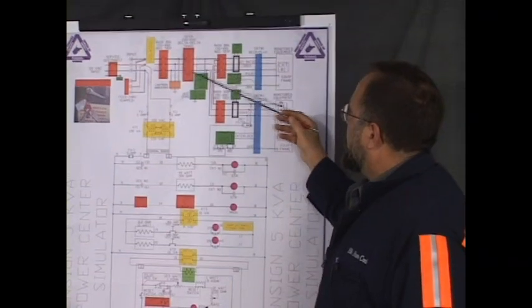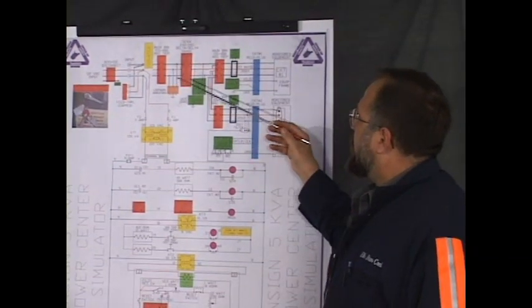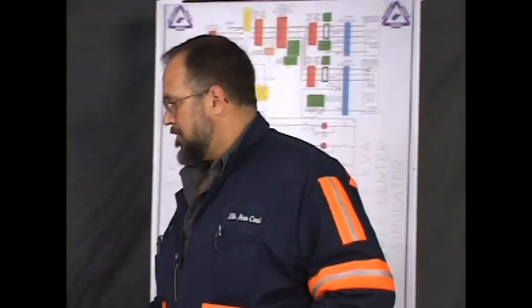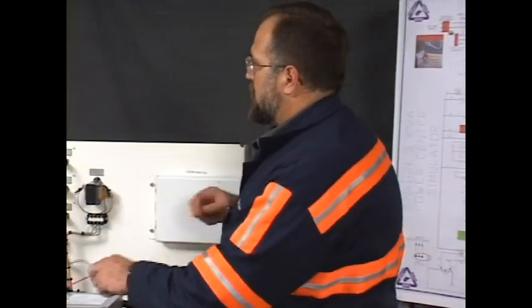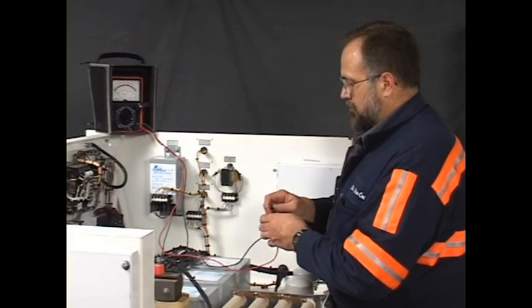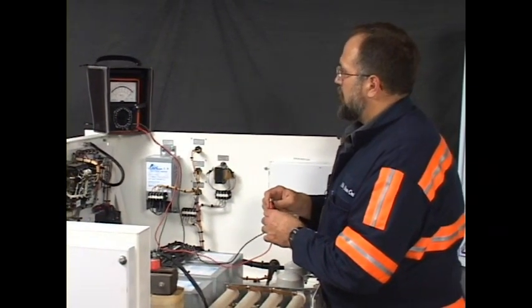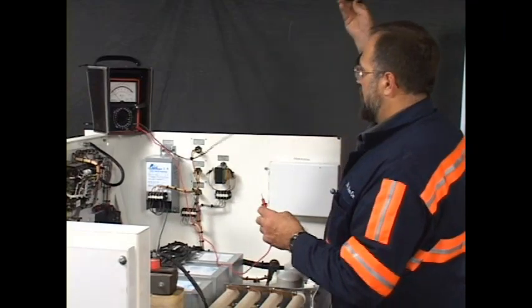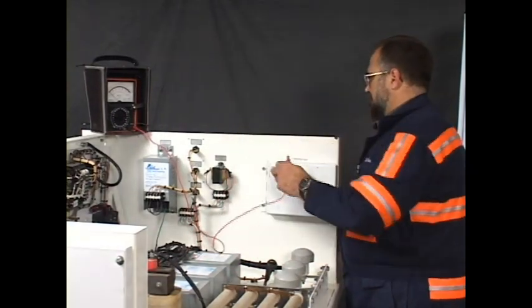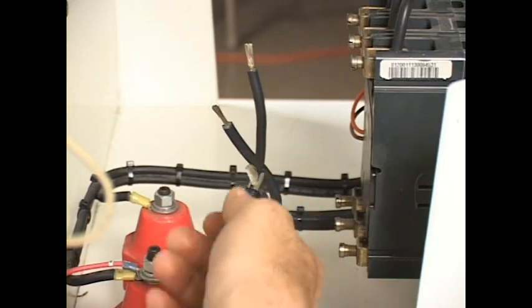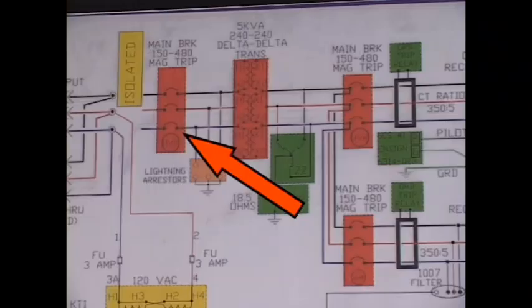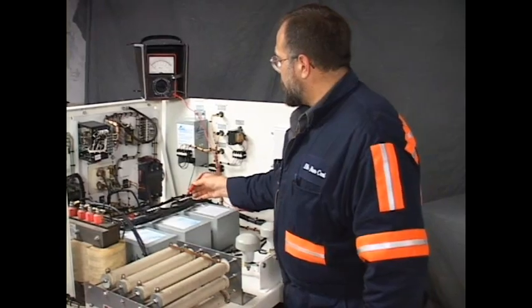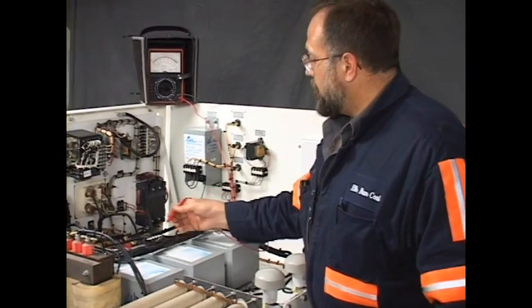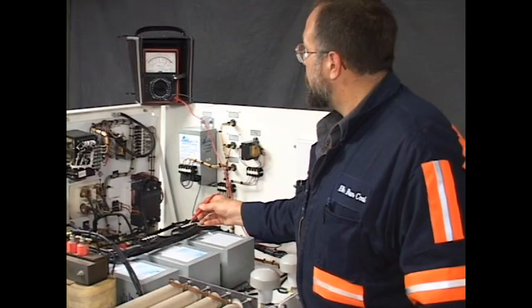The high voltage input to the transformers from the main breaker. To do that, we're going to take our instrument, zero it, and we have a 0, properly calibrated. Okay, I'm going to attach the black alligator clip to the first phase. Looking on the drawing, that would be right here, bottom of the main breaker. We'll read to the first transformer, and we have no power, or no continuity, I should say.